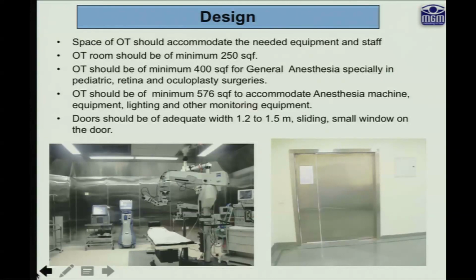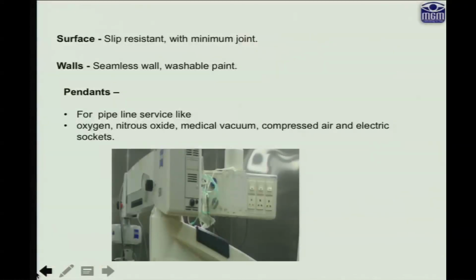Space of the OT should accommodate the needed equipment and staff. The OT should be of a minimum size of 250 square feet. For general anesthesia patients like pediatric, retina and oculoplasty, the size should be 400 square feet. To accommodate anesthesia machine, equipment, lighting and other monitoring equipment, the size should be 576 square feet. Door should be of adequate width, 1.2 to 1.5 meters, sliding, with a small window on the door. Surface should be slip resistant with minimum joints, seamless wall and washable paint. Pendants are for pipeline services like oxygen, nitrous oxide, medical vacuum, compressed air and electric sockets.